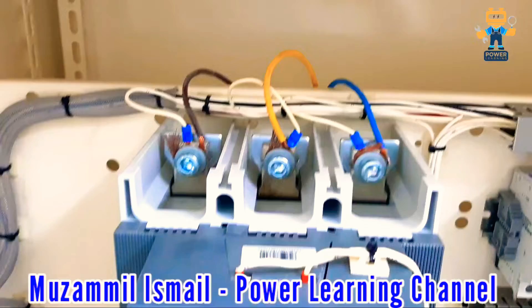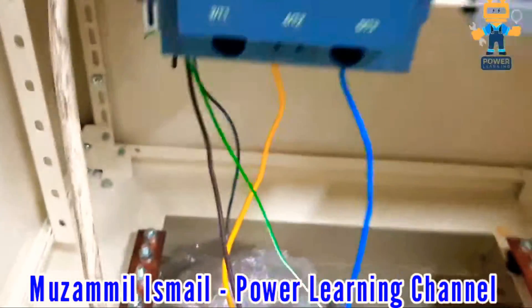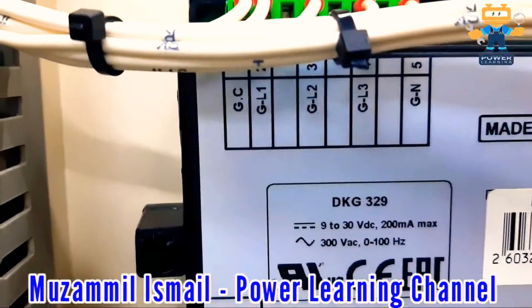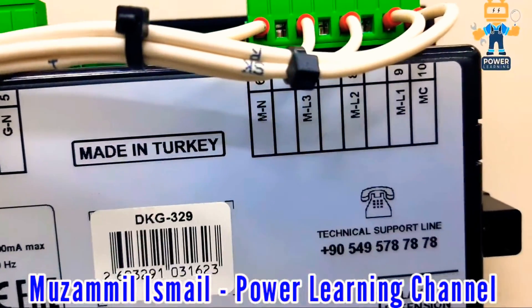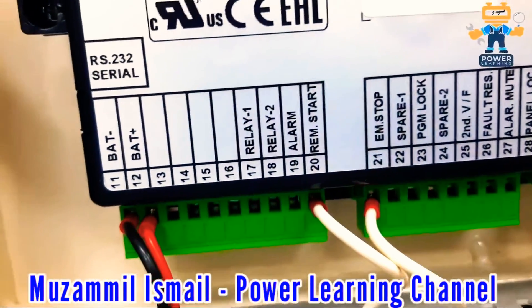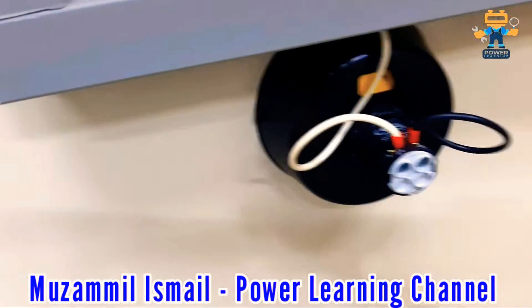Here is our genset contactor where we connect our testing wires. This is our load side with three CTs. This is our mains contactor where we connect the mains wire. On the controller back side, we have GL1, GL2, GL3, and GN for generator supply connection; mains L1, L2, L3, and mains neutral; MC is the contactor command; battery negative, battery positive; relay 1, relay 2; alarm; remote start; emergency stop; and CT connections for three CTs — six wires. We also have three indication lamps and a selector switch.